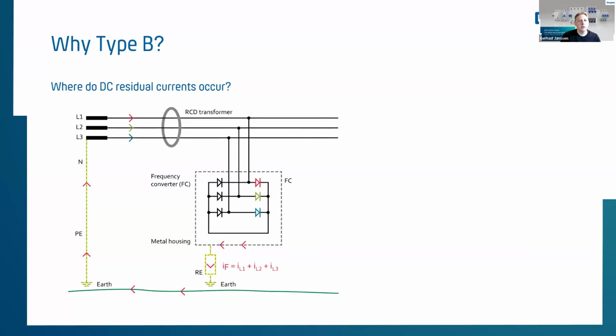There was a construction site on a German construction site. There was a big crane installed. The motor was driven by a VFD, and they had an electrical shock accident. At the end of the 1990s, they were not able to detect why this happened, because there was a type A RCD installed. So everybody was thinking they were safe, but after checking the whole system, they found out that direct DC currents were the source of the electric shock.